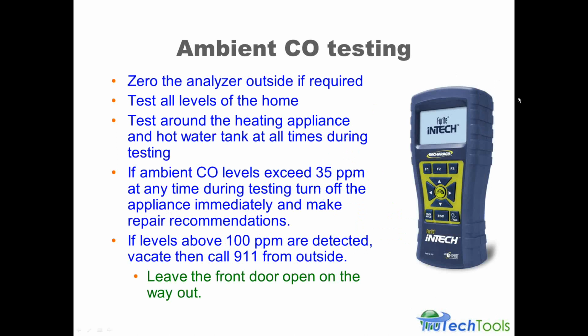So ambient CO testing now. We want to zero the analyzer outside. It's important to test at all levels of the home, even though the CO is not going to pool at the higher or lower levels. It does move through with the ventilation air moving through the structure. So you do want to test at all levels. You're never sure where you're going to find it due to vent leakage or propagation due to the air handling system.